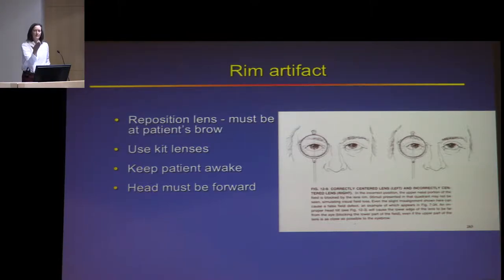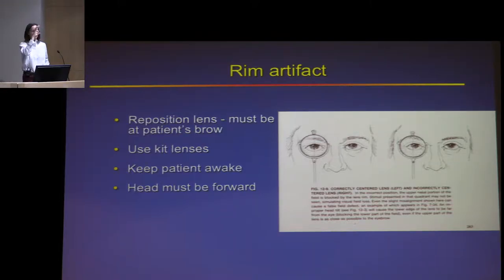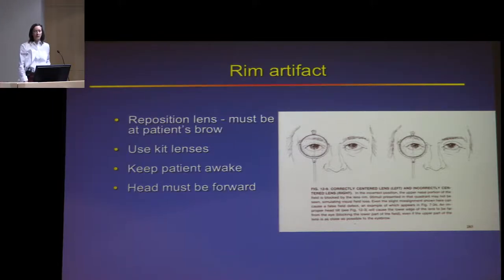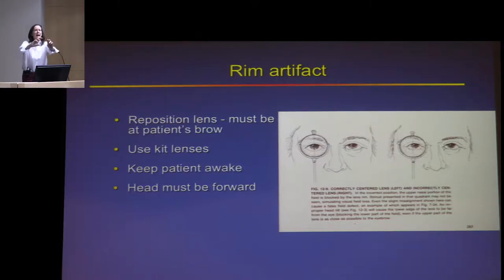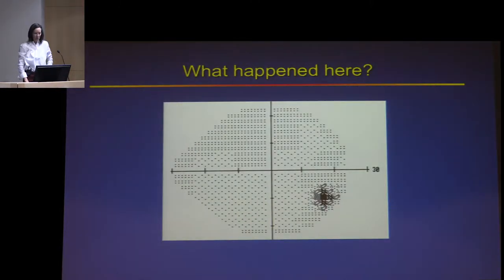With rim artifact, most often what's happening is that the corrective lens is on its little stand right up against the patient, and then over the course of testing the patient drifts back and ends up looking through the ring of the lens holder. It's best to use the machine's lenses; if you can't get the astigmatism correction you need, use the patient's own glasses as long as they're correctly positioned. Keep the patient's head up against the forehead rest — just like when you're trying to do a slit lamp exam and the patient keeps falling back.